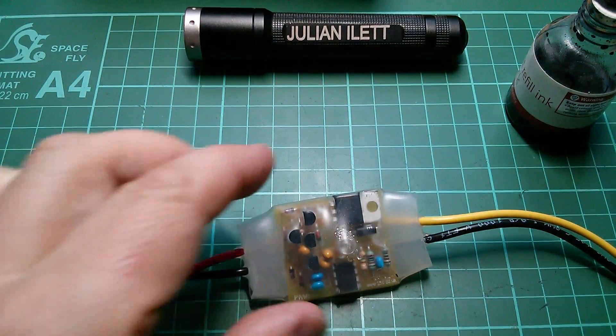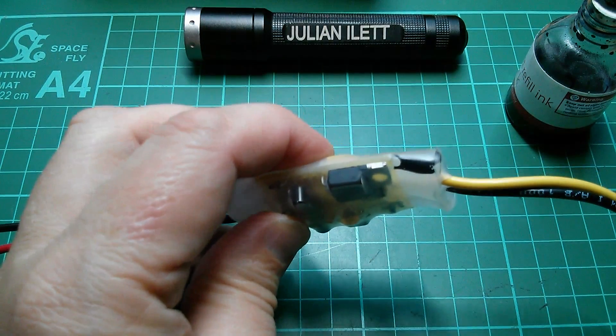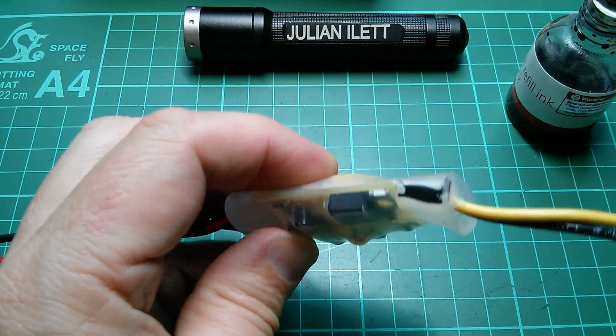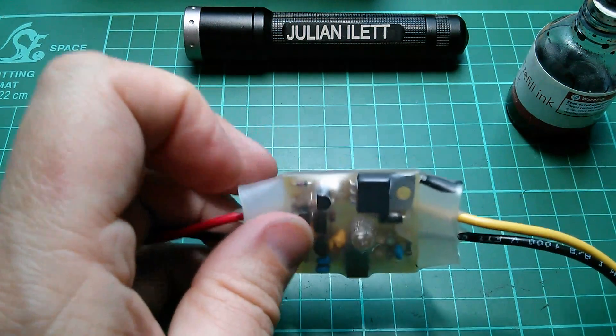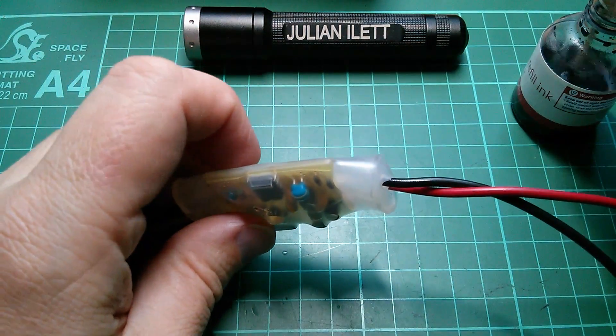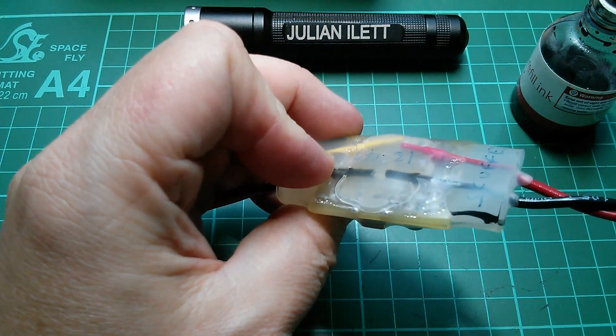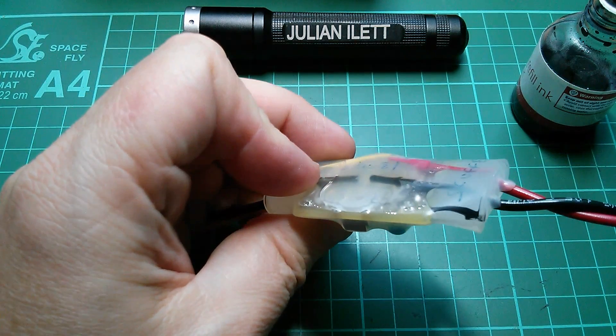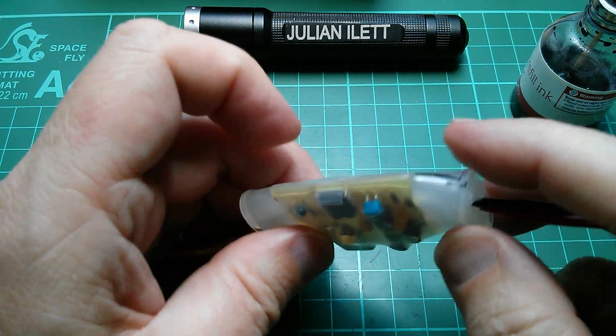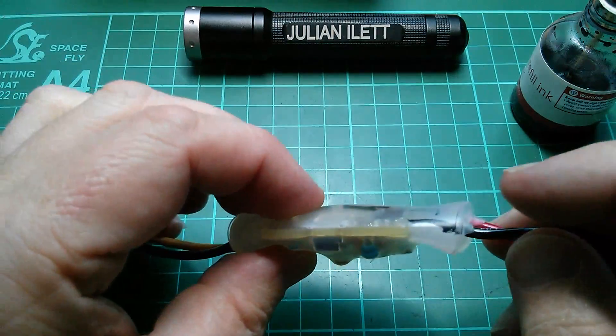I'm not sure how effectively I can dab ink into this, but oh — very effectively it would seem. You can see that the ink has run right through that channel and gone inside the unit. Let's just try that again on the opposite corner, which I also think has got a breach in it. Put a dab of ink in there — and yeah, that's run right through what's clearly an open moisture channel. It's fairly obvious that moisture can get in through those ends.